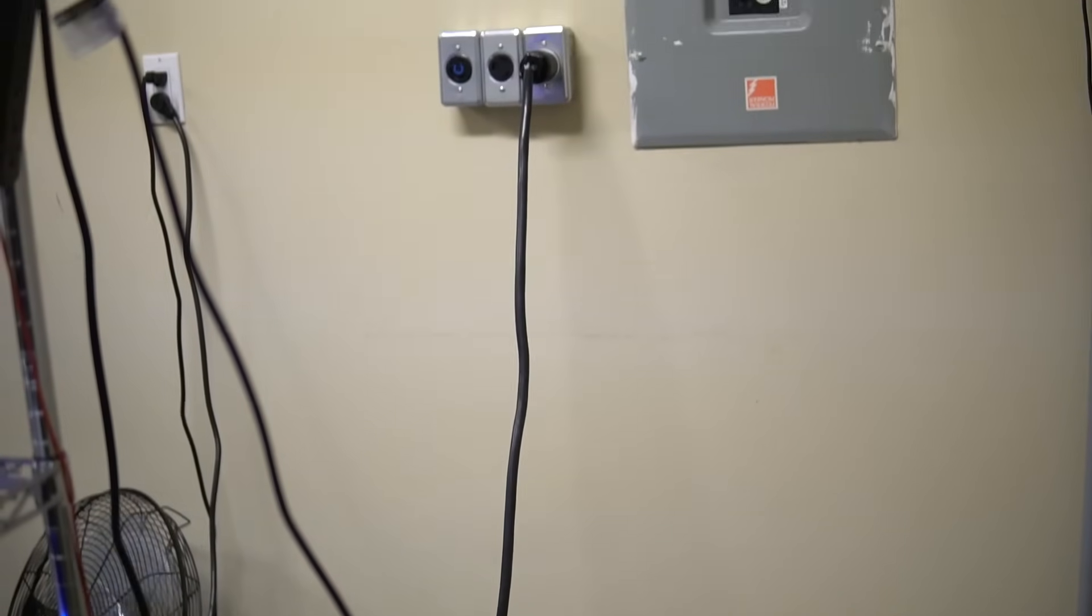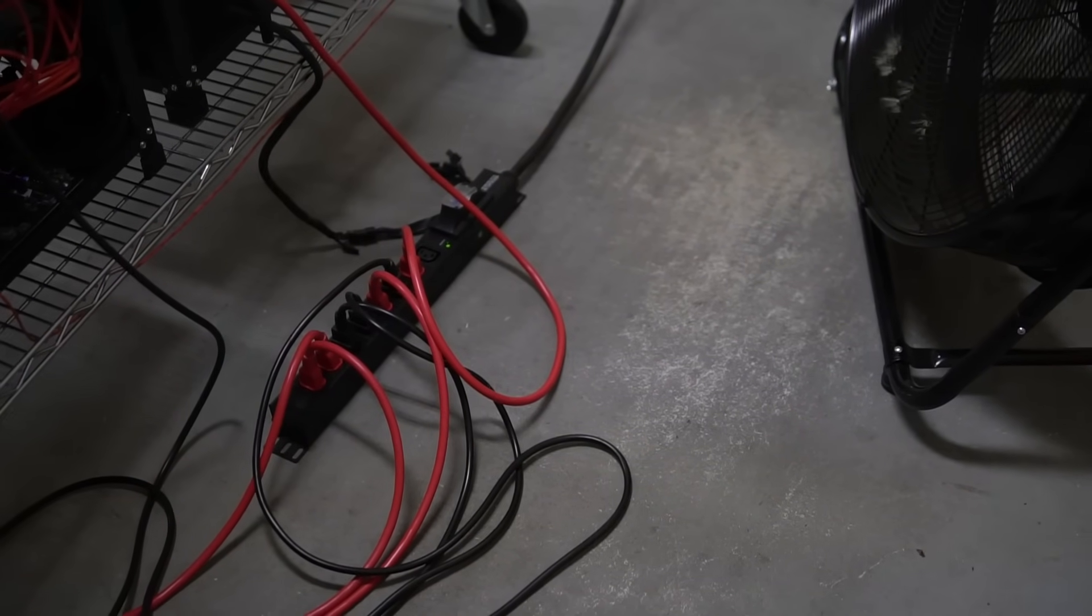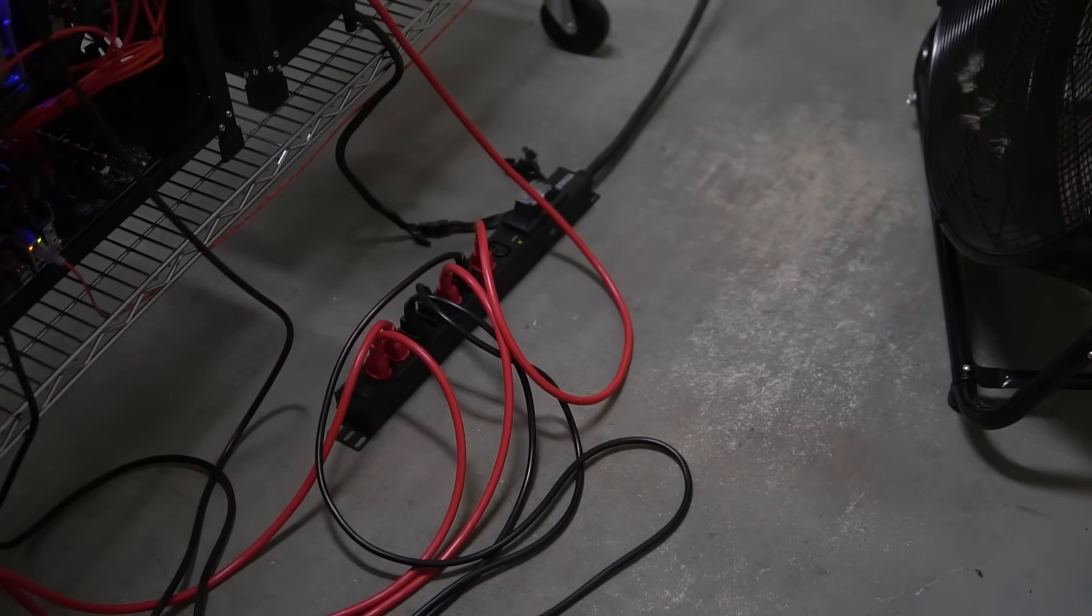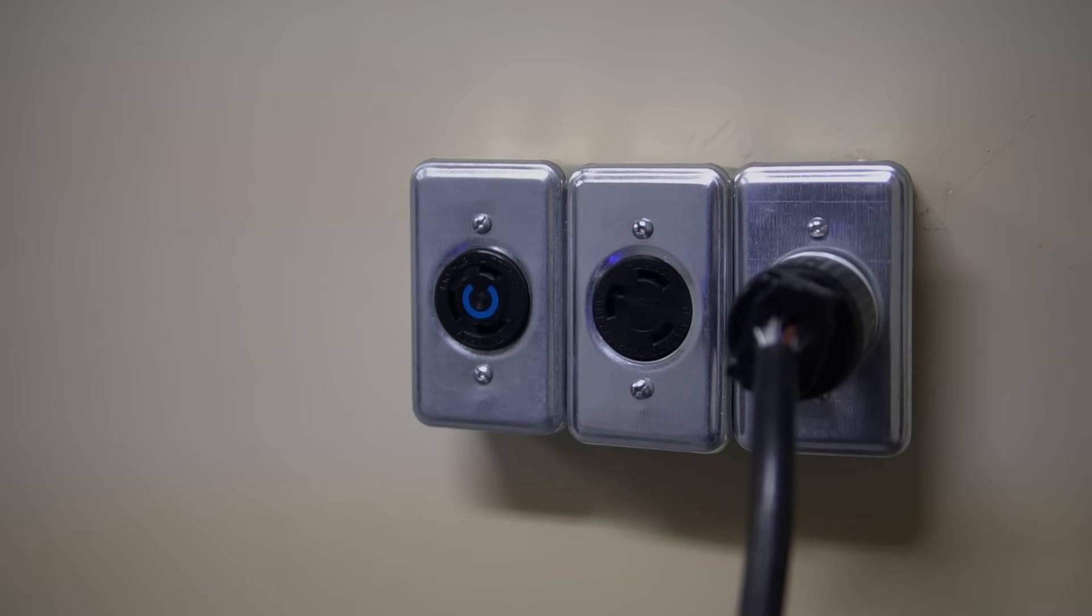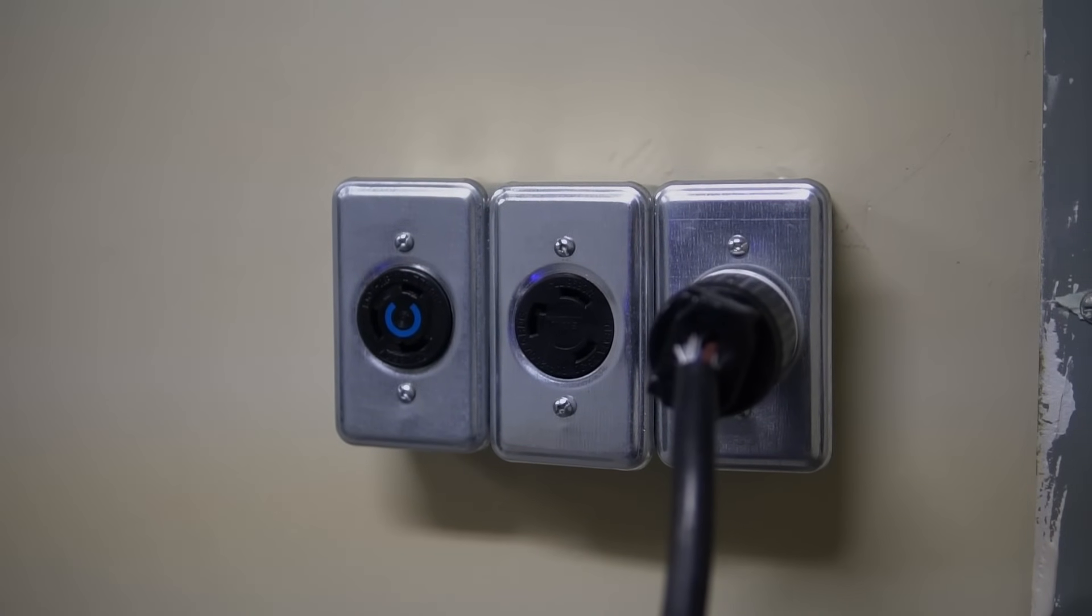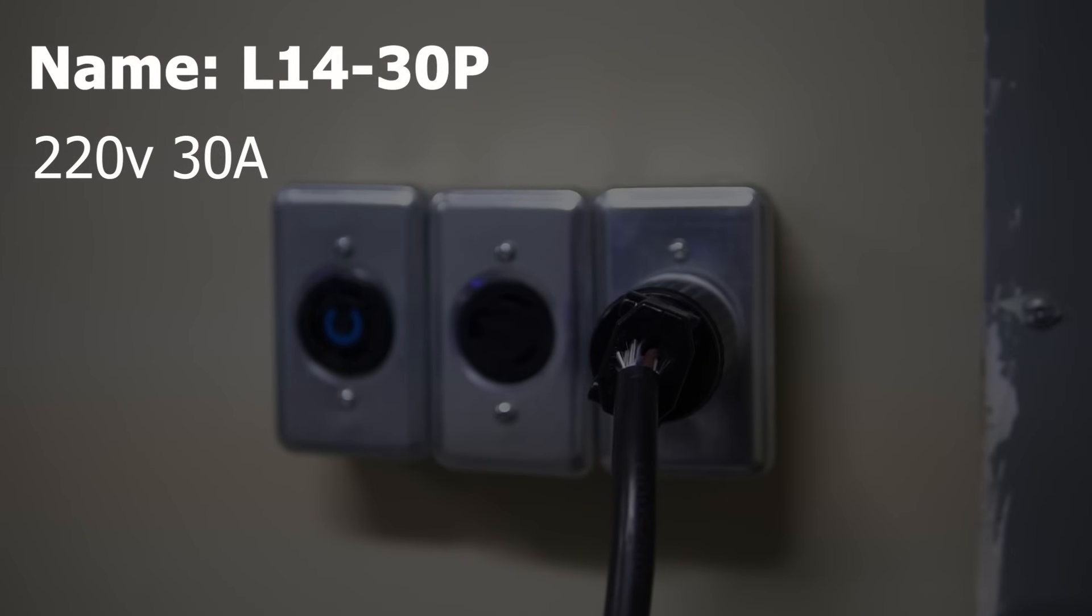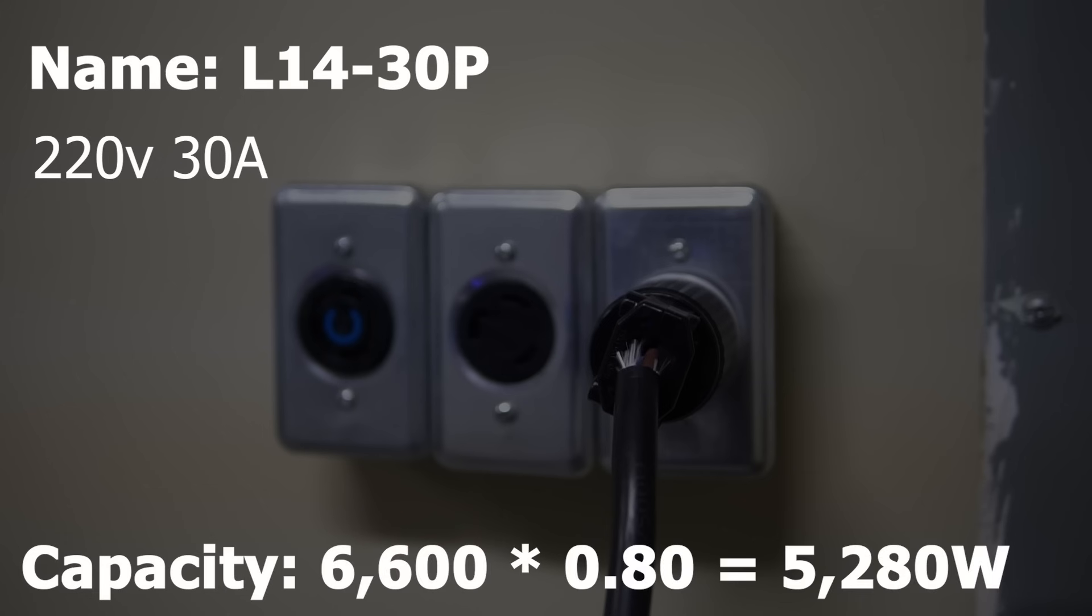So these plugs are generally 220 volts 30 amp, which means if you want to know how much power you can run on these, you just multiply 30 by 220, and then you only use 80% of the result.